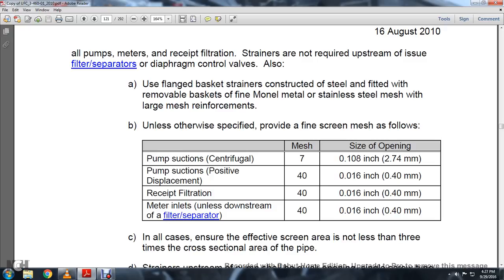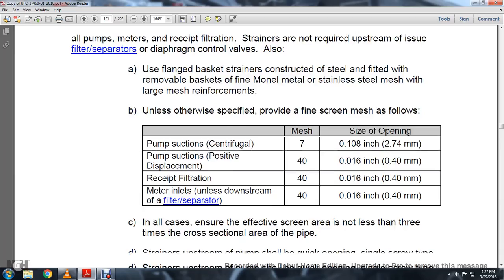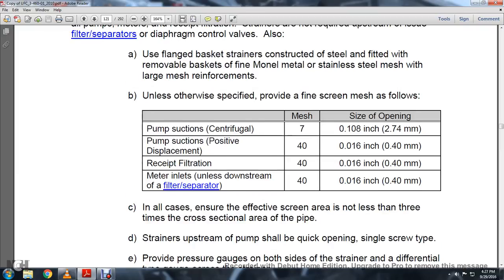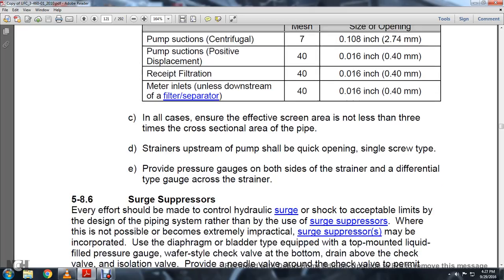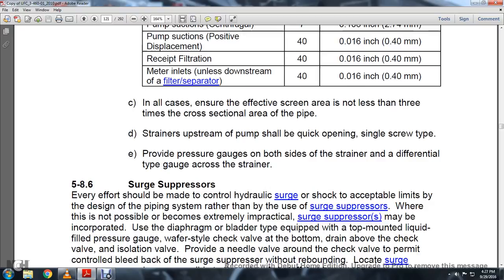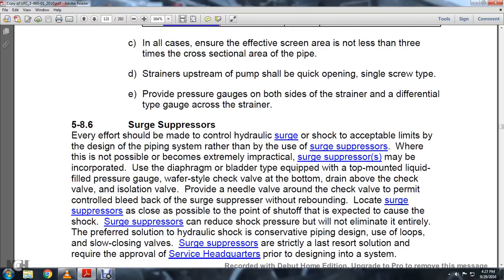Receipt filtration, 40 mesh, 0.016 inch. Meter installation, unless a downstream filter, 0.64 mesh 40, 0.16 thousandths of an inch. In all cases, ensure the effective screen area is not less than 3 times the cross-sectional area of the pipe. Strainers upstream of the pump shall be quickly opened, single screw type, provided with pressure gauges on both sides of the strainer, differential type gauge across the strainer.